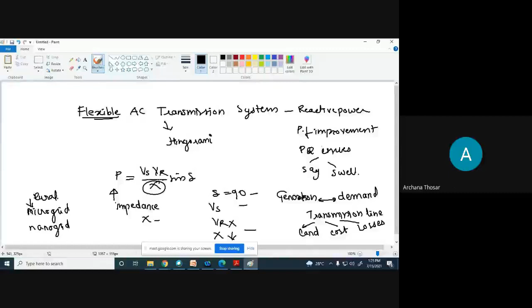So we can reduce the X. But for a huge transmission line, permanently adding some reactive compensating element will not help, because there will be continuous losses, and switching of those devices will be required. Also, the reactive power demand keeps changing.